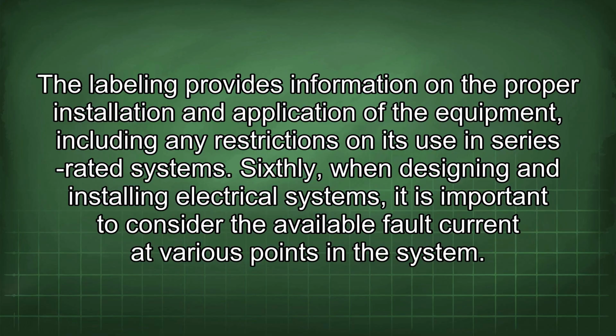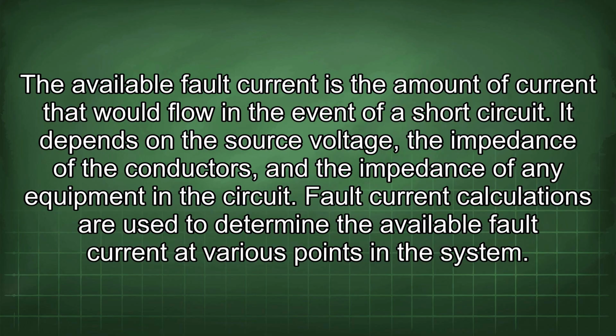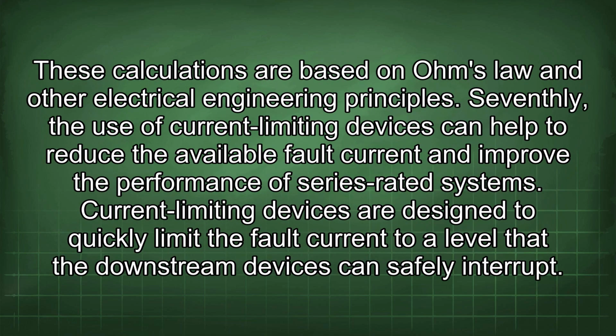Sixthly, when designing and installing electrical systems, it is important to consider the available fault current at various points in the system. The available fault current is the amount of current that would flow in the event of a short circuit. It depends on the source voltage, the impedance of the conductors, and the impedance of any equipment in the circuit. Fault current calculations are used to determine the available fault current at various points in the system. These calculations are based on Ohm's law and other electrical engineering principles.